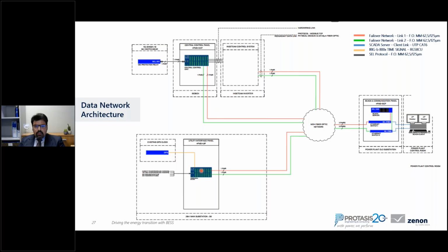It is also a cell action device which collects measurements and statuses of grid interconnection base and provides this information to the central control unit as well as to the SCADA system. The communication network is a redundant fiber optic network and is based on layer 2 managed Ethernet switches. Of course, we have a SCADA server, which is a rugged and industrial computer which hosts the zenon Energy Edition software. The operators are interacting with the SCADA system via one client with 2 screens located at the control room of the refinery. The utilized communication protocols are Modbus and IEC 61850.